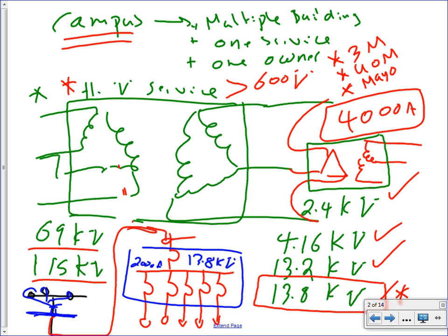If you have a termination box, like we do, from the transformer to the termination box, you put the conduit and Xcel will pull their own cables. From the termination box into my building, I put the conduit and I install the conductor. So these are the arrangements that you do with the Xcel.